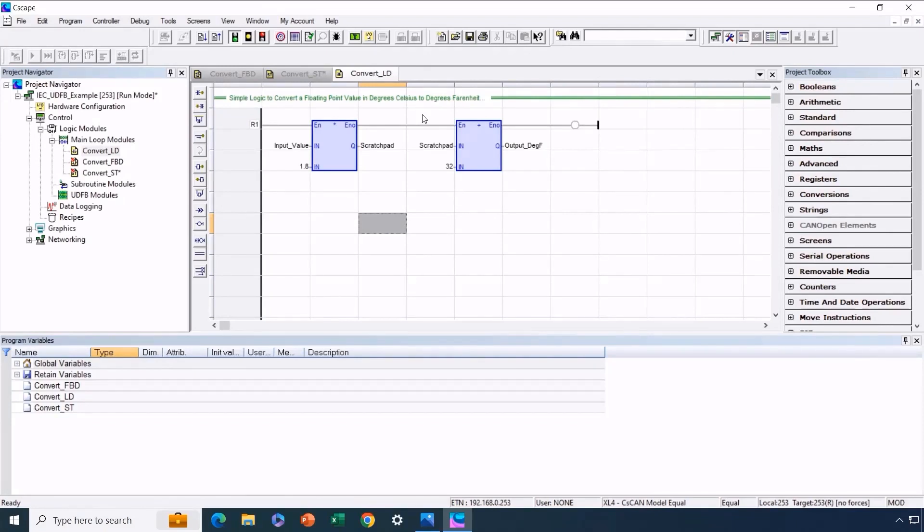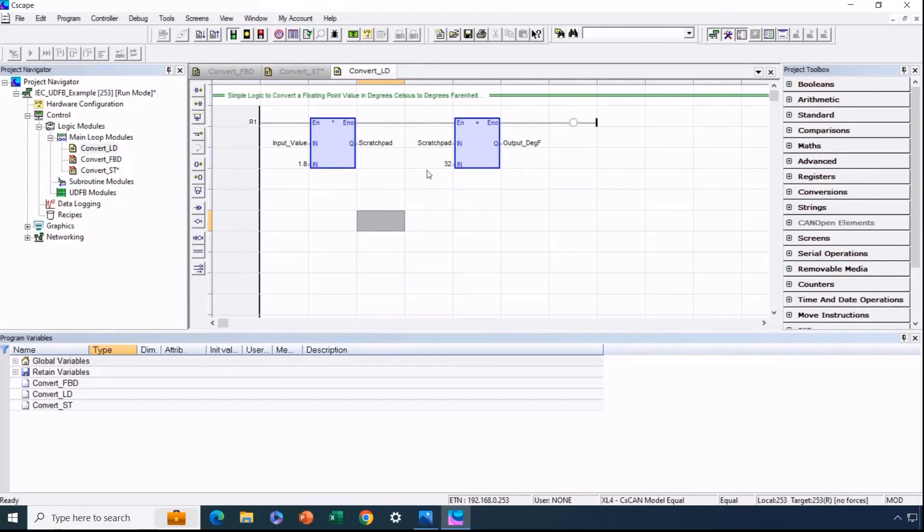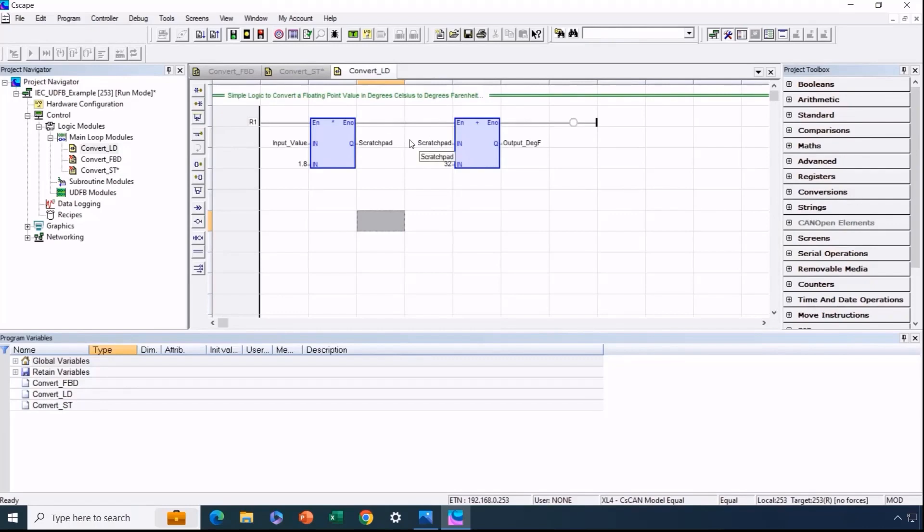The objective is to showcase the process, so now we'll look at what steps we need to take when it comes to creating a UDFB. The initial stage involves isolating, writing and thoroughly testing the logic, which we have already done. Moving on, the next step is defining the input, output and internal variables. In this case, our function block's input variable is the original value in degrees Celsius. The output variable is the converted value in floating-point degrees Fahrenheit. Additionally, for the ladder implementation, we require an internal scratchpad floating-point variable for intermediary calculations between multiplication and addition. Essentially, we're referring to one input, one output and one internal variable in this simple instance.